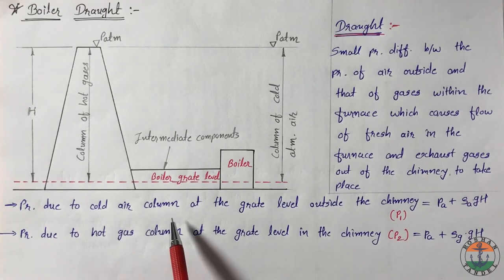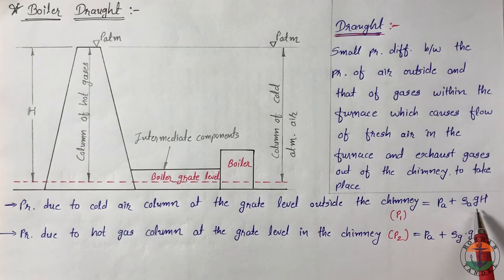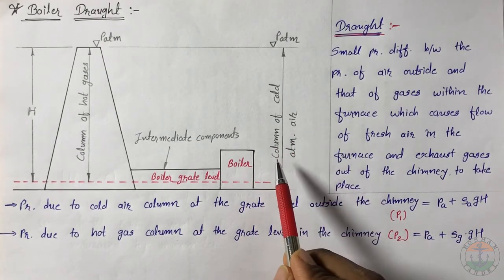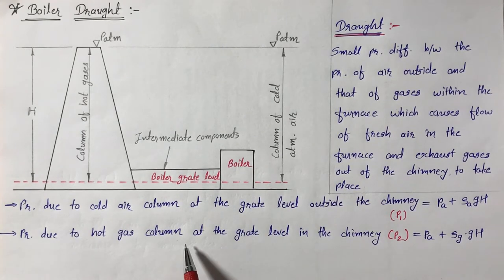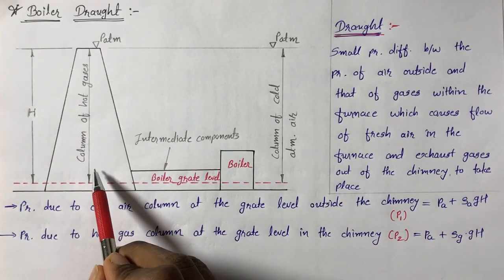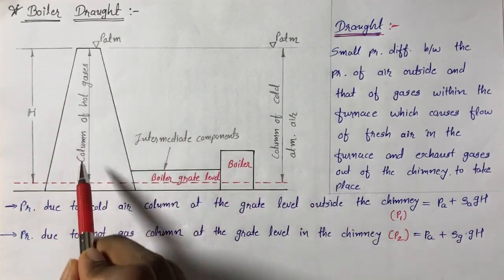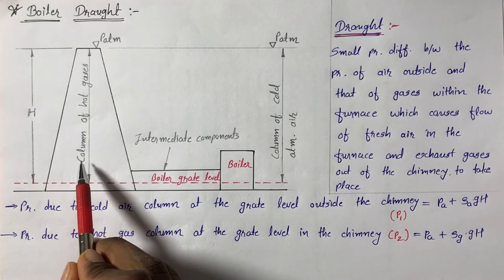PA is the atmospheric air pressure at the top of the chimney. Pressure due to cold air column at the grate level outside the chimney is equal to PA plus rho_A into G into H, where rho_A is density of air outside the chimney. Pressure due to hot gas column at the grate level inside the chimney, P2, is equal to PA plus rho_G into G into H, where rho_G is the average density of hot gases.